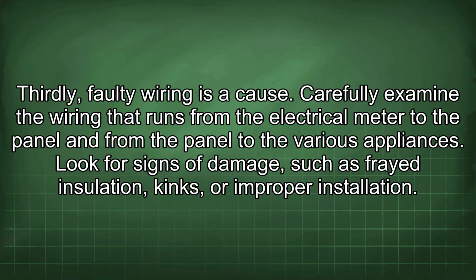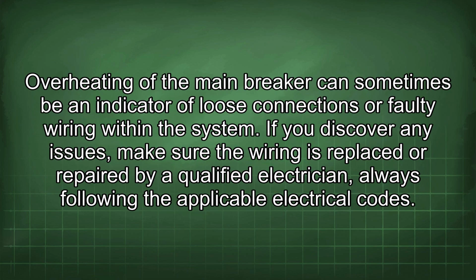electrician. Thirdly, faulty wiring is a cause. Carefully examine the wiring that runs from the electrical meter to the panel and from the panel to the various appliances. Look for signs of damage, such as frayed insulation, kinks, or improper installation. Overheating of the main breaker can sometimes be an indicator of loose connections or faulty wiring within the system.